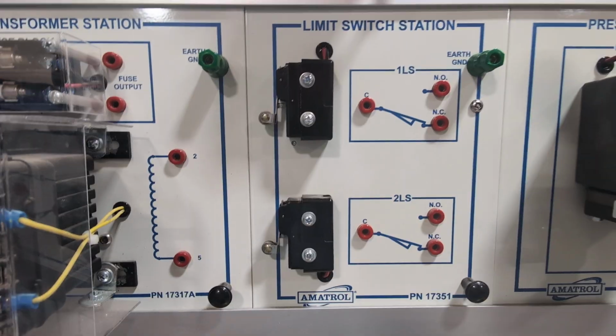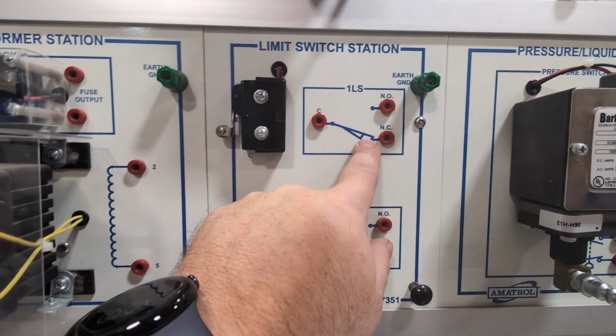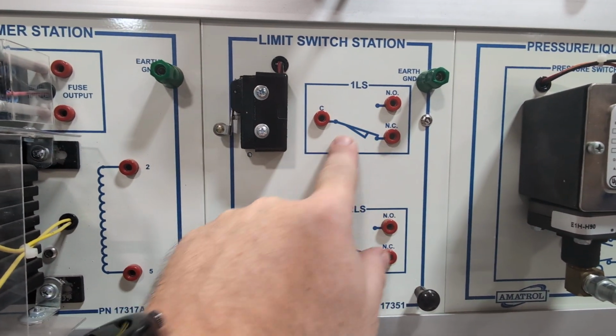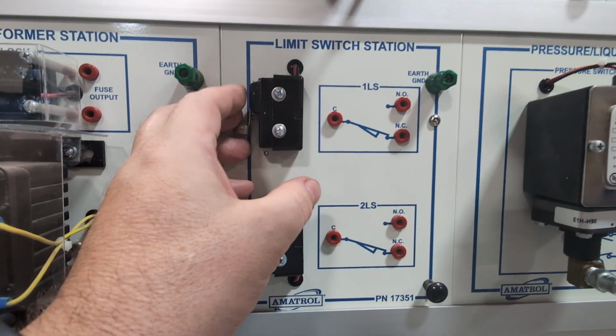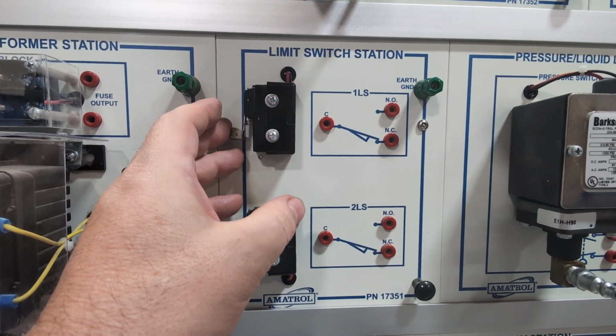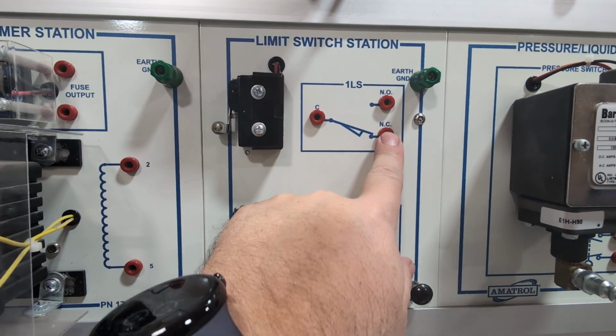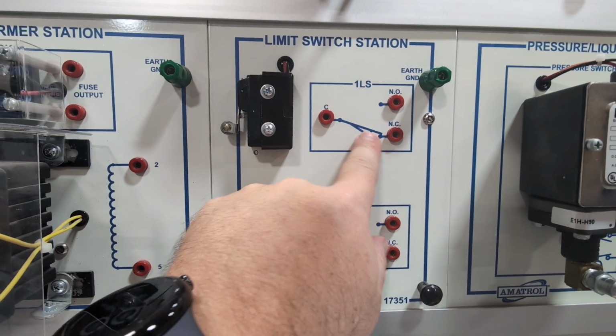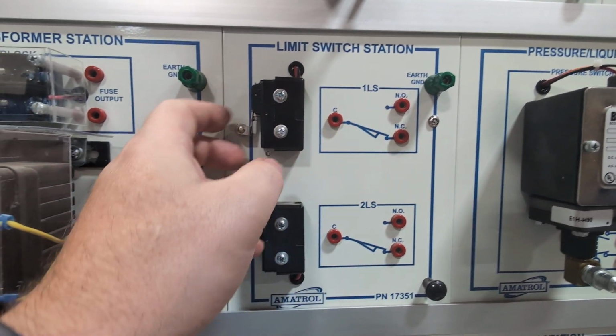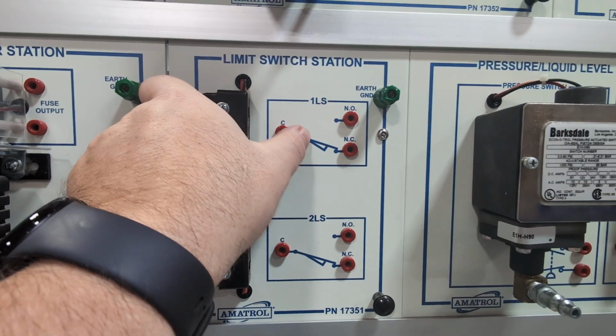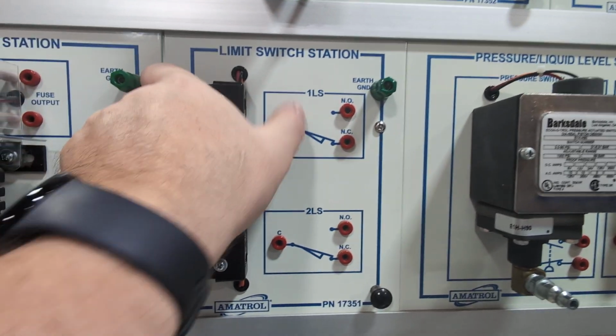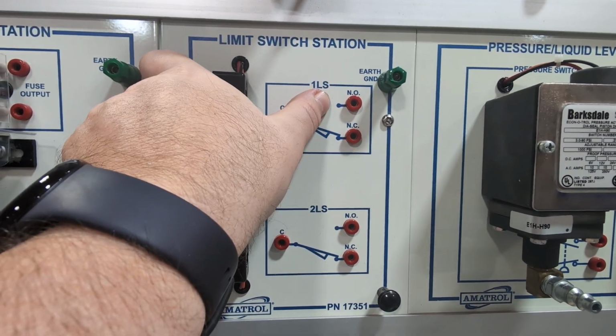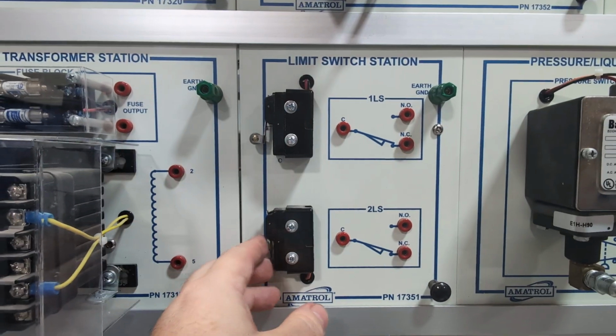This is called limit switches. Internally, how is this physically done? So right now, in a relaxed state without power or movement, I am in the normally closed position, NC. Just like a light switch, on and off. When I push this in, it moves from NC to normally open. Okay, so it comes off NC to normally open. These are called limit switches.